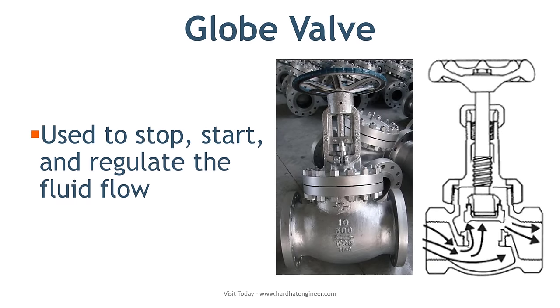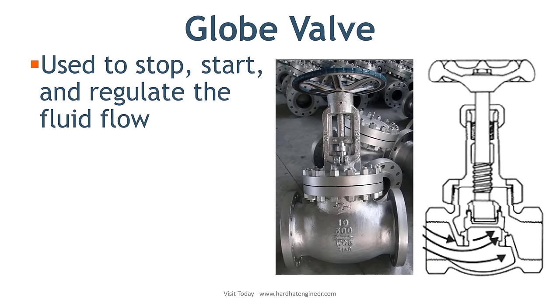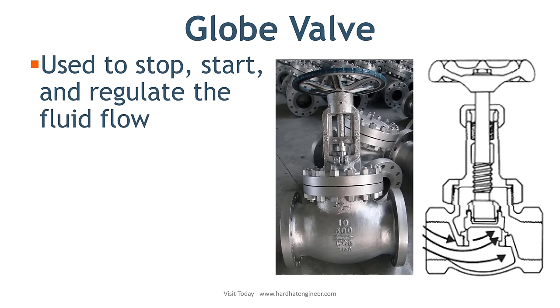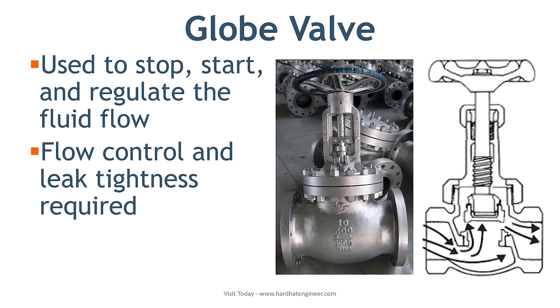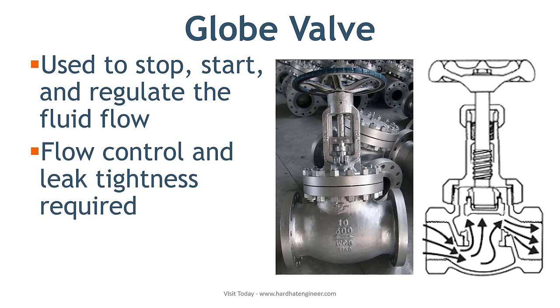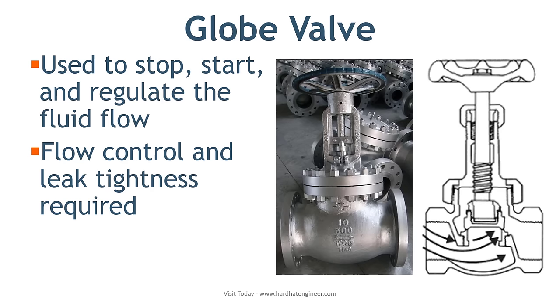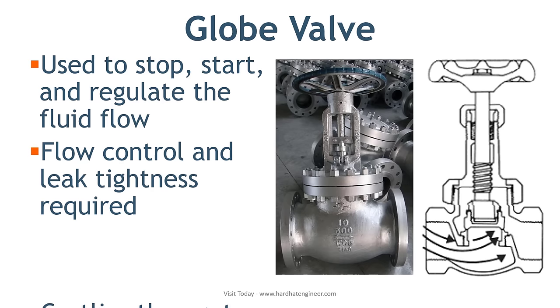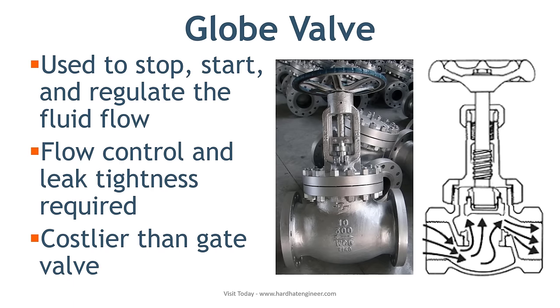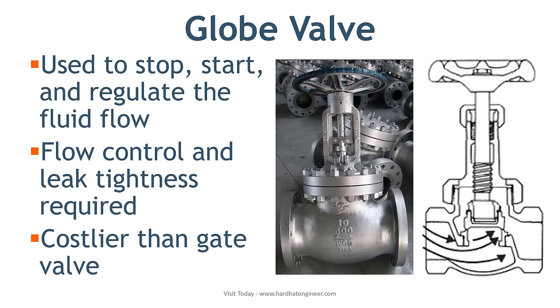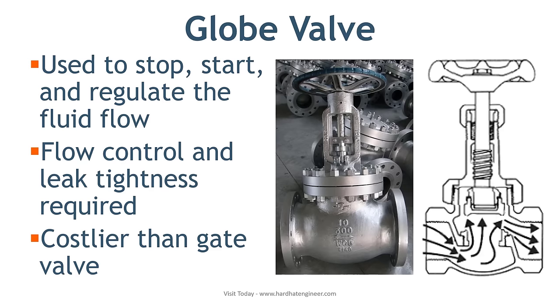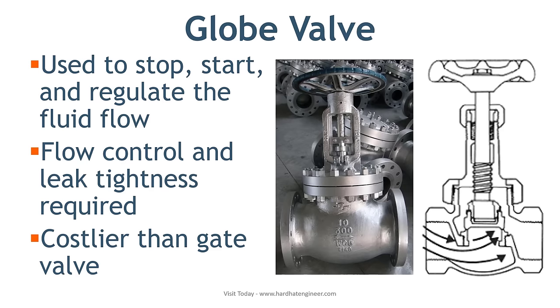Globe valve is used to stop, start, and regulate the fluid flow. Globe valves are used in a system where flow control is required and leak tightness is also necessary. Globe valve provides better shutoff as compared to gate valve and it is costlier than gate valve.